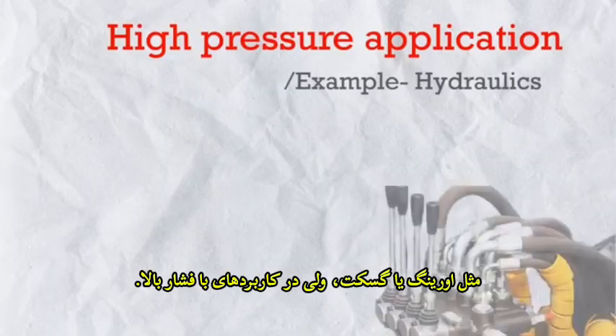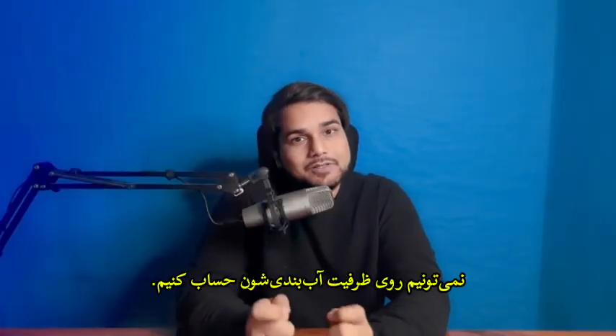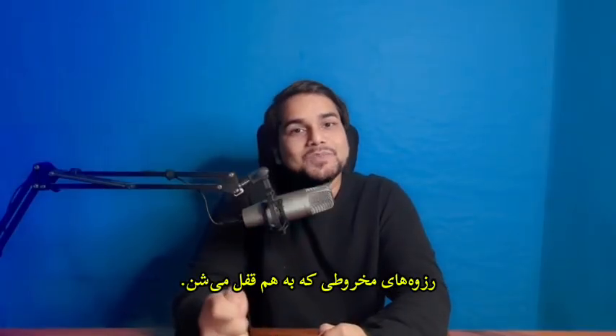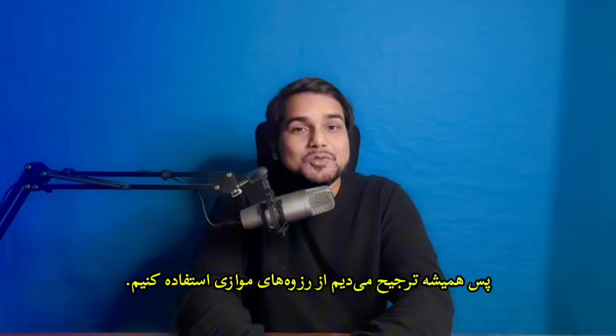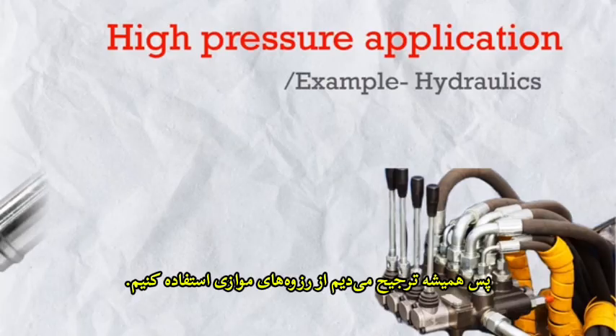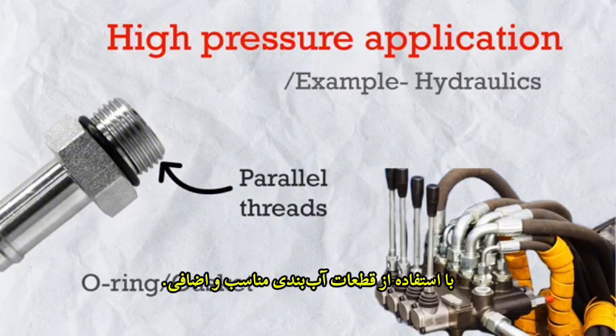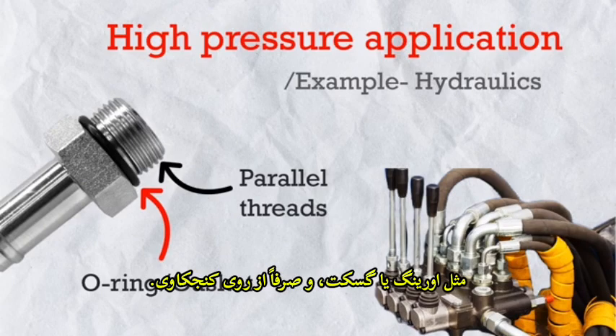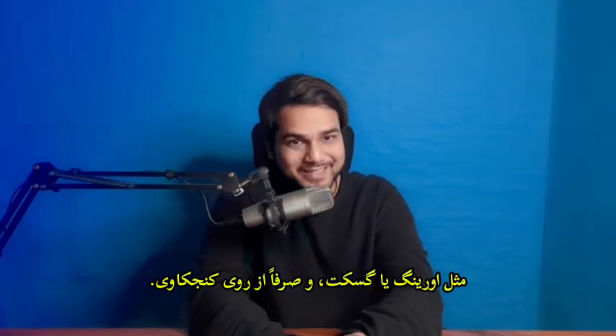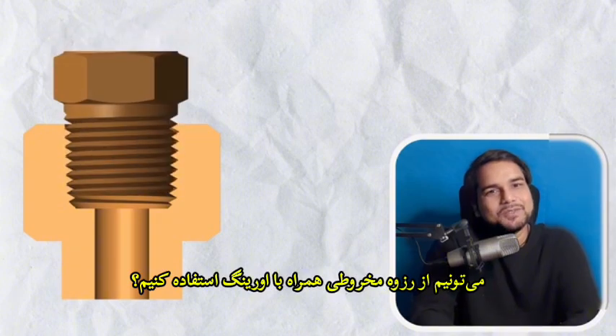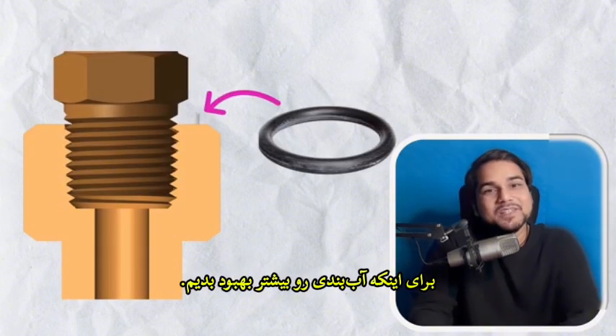But in high pressure applications, we cannot trust the sealing capacity of the taper thread interlocking. So we always prefer to use parallel thread with extra proper sealing elements like O-ring or gasket. And just for curiosity, can we use taper thread with O-ring to further improve the sealing?